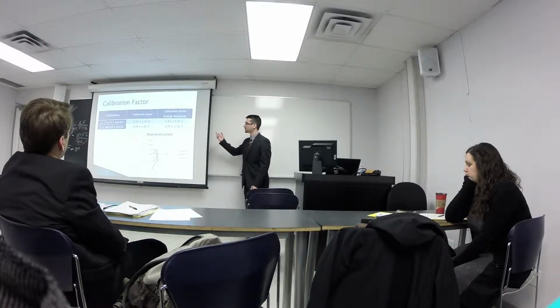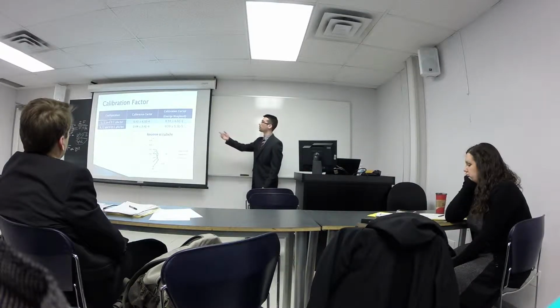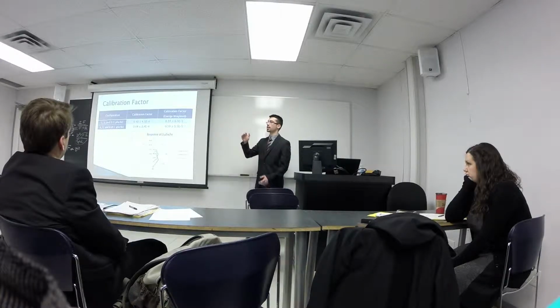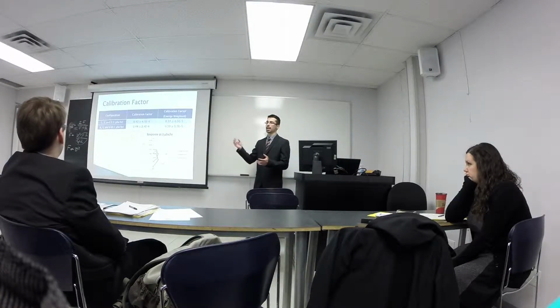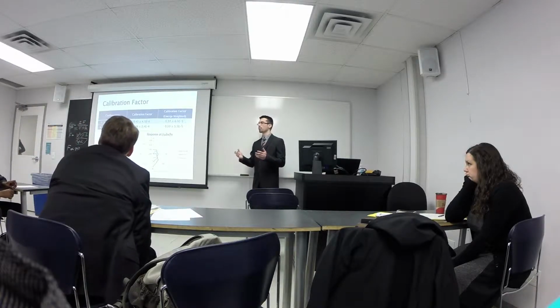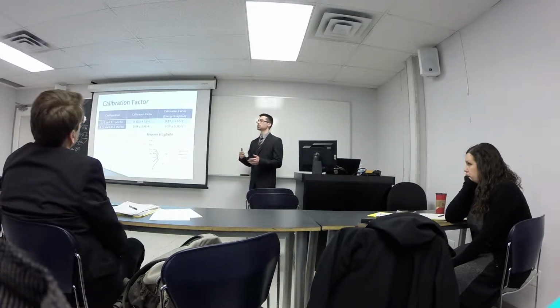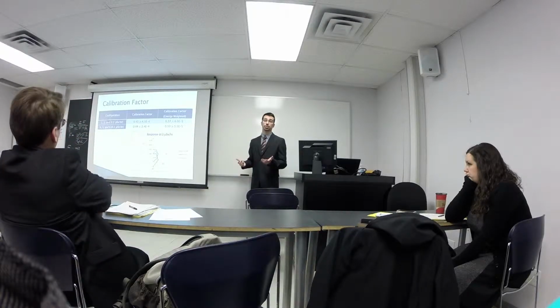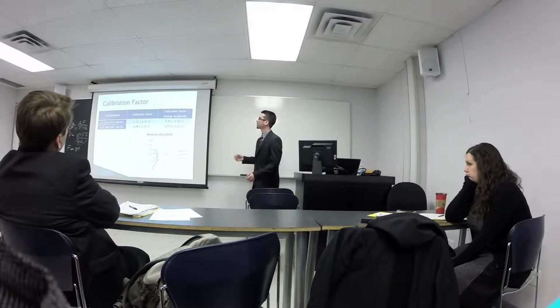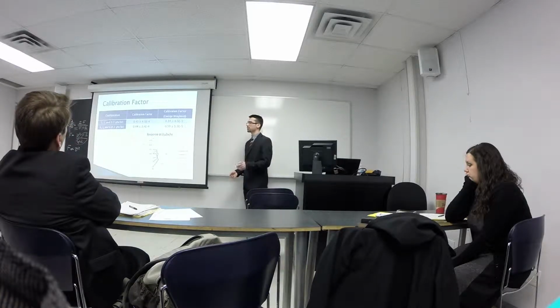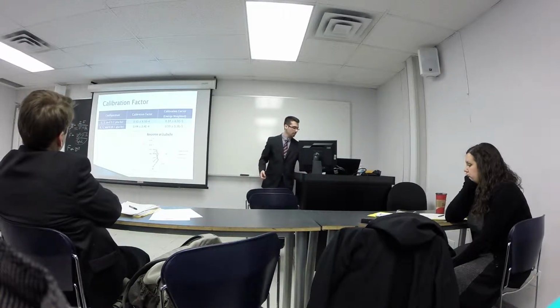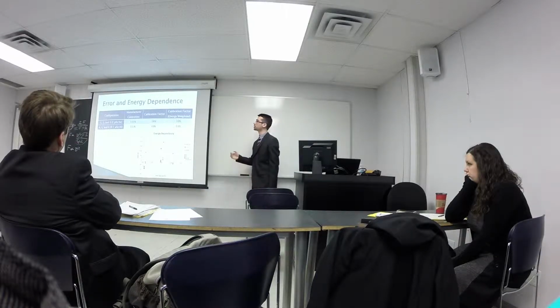So what I was able to do is average this over energy and angle to come up with a calibration factor. It could actually be done at a different dose rate, because we could analyze the counts coming into the detector and then have a rough idea of what dose range we would be in, and then apply a specific calibration factor to that dose rate. But as you can see, they were very similar. I also tried an energy-weighted calibration factor, which was recommended by faculty. Both of them reduced the percent error quite significantly, but the regular average performed better if we averaged between the two of them. I was able to reduce the error almost 100% after calibration.